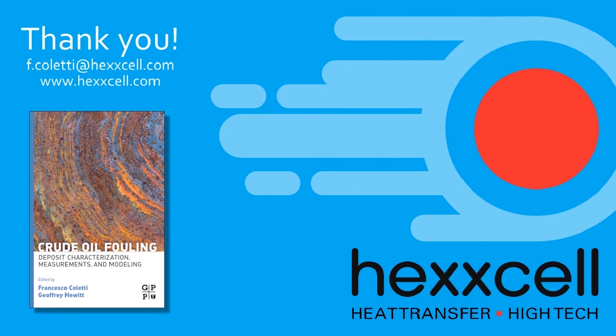Yes, we definitely looked at coatings. Coatings can be applied very successfully, and they do provide significant benefits compared to the cost of having to open up the heat exchanger and clean it, which also has some safety implications very often, downtime, and so on. However, coatings are not available for all possible applications. Especially when you start talking about heat exchangers at 300 degrees C and 30 bars, high temperatures with hydrocarbons in a very corrosive environment, it's difficult to find a heat exchanger coating that will fit the bill.